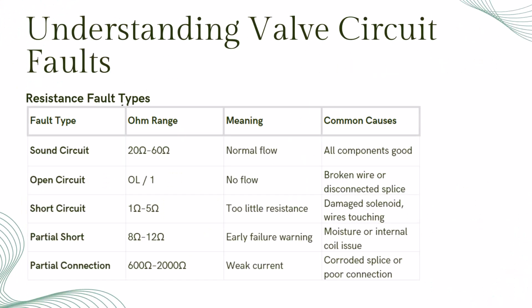Once the controller checks out, we move to the valve circuit and use the resistance readings to interpret what's happening inside the wiring. A healthy valve circuit reads between 20 and 60 ohms. If you see OL or 1, you've got an open, a break or disconnected wire. If the number drops below 20 ohms, that's a short. Electrons are taking a shortcut somewhere. Extremely high readings mean a partial connection, usually corrosion or a poor splice limiting the flow of current. By understanding these resistance ranges, you can tell whether your issue is mechanical or electrical before digging up a single wire.